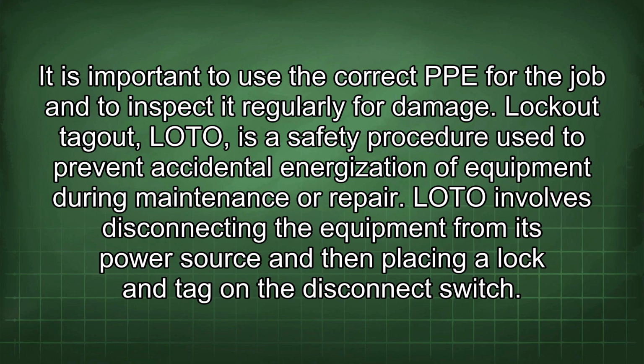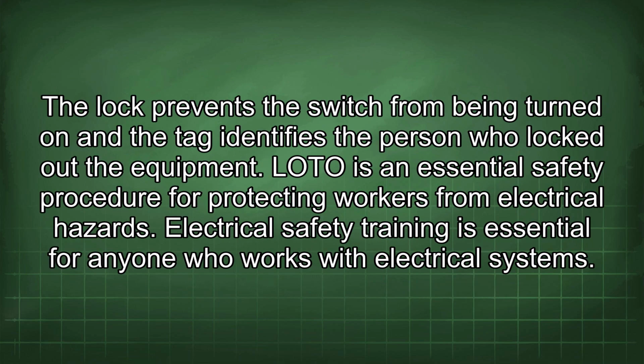Lockout-tagout (LOTO) is a safety procedure used to prevent accidental energization of equipment during maintenance or repair. LOTO involves disconnecting the equipment from its power source and then placing a lock and tag on the disconnect switch. The lock prevents the switch from being turned on and the tag identifies the person who locked out the equipment. LOTO is an essential safety procedure for protecting workers from electrical hazards.